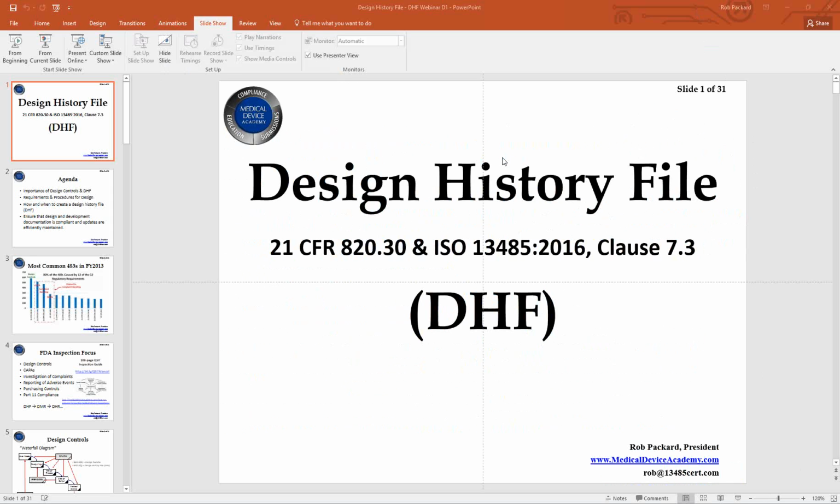You're also going to be assessing whether all the risks that you are seeing in reality match up with what you estimated in the design project. So are the severities correct? Are you missing some risks? So some hazard wasn't identified during the risk management process and now it's showing up. Are there some indications for use that you didn't anticipate, some off-label or foreseeable misuse? That's often very common, foreseeable misuse. So those are some things that should be included for the risk management plan for post-market surveillance.